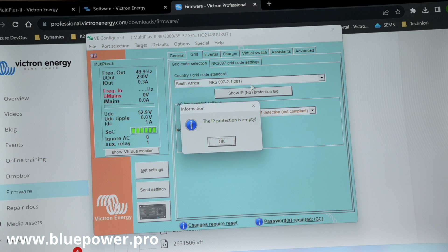Over here, right below that, we've got our IPNS logs, so that's protection logs. If you've got a running system that has connected to the grid and it's disconnected or whatever, over here if you open this up, it will show you all the most recent disconnect reasons from the grid. If it's a drop in voltage or drop in frequency, or a rise in voltage or rise in frequency, it will indicate it over here. But for that you physically have to log in on VE Configure to access that.